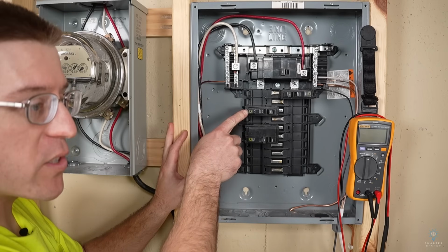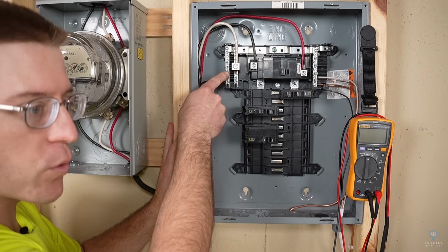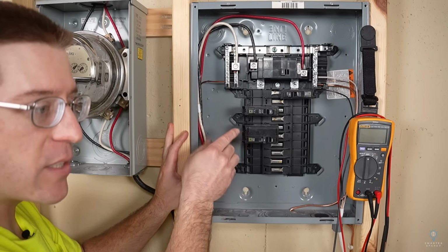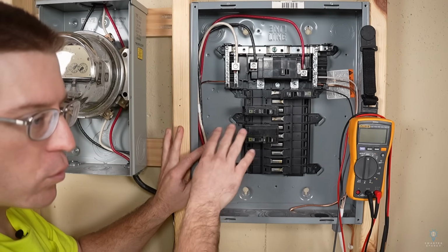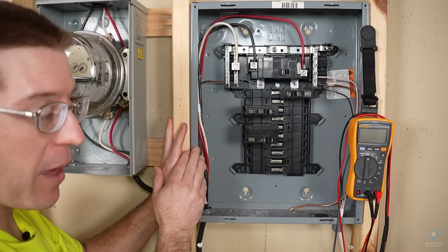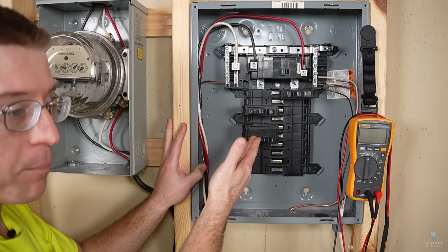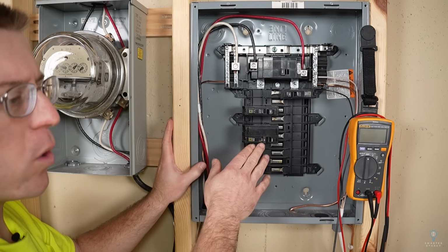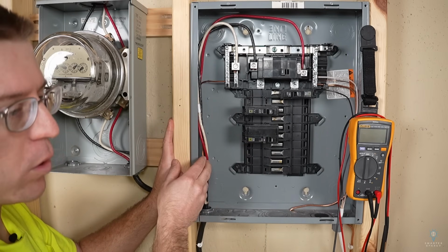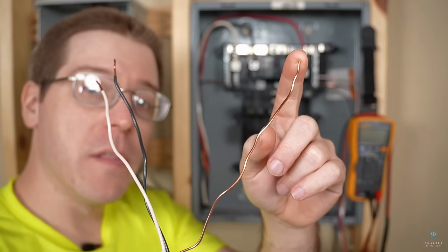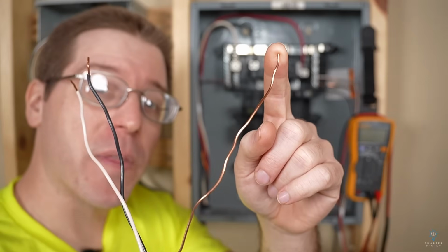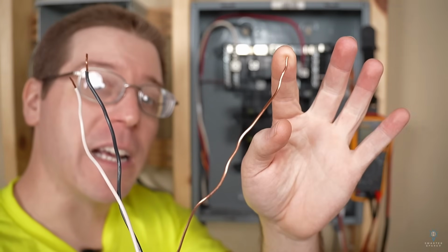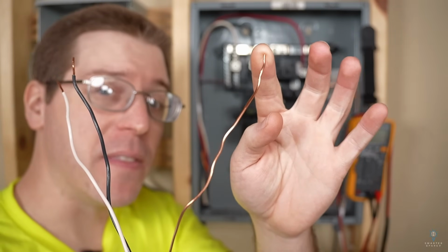For 120 volt circuits, the return path is the neutral, and for 240 volt circuits, the current flows out on one hot and back to the other hot. The neutral is not part of the current path. Now again, some 240 volt appliances include a neutral, but that's only so they can run internal controls off of 120 volts. The equipment grounding conductor is not part of normal current flow. They are there strictly for safety, providing a low resistance return path in the event of a fault.